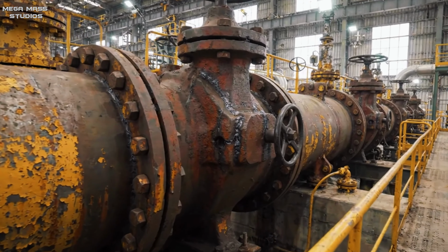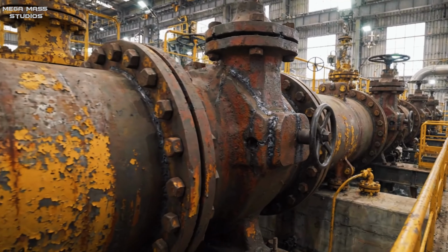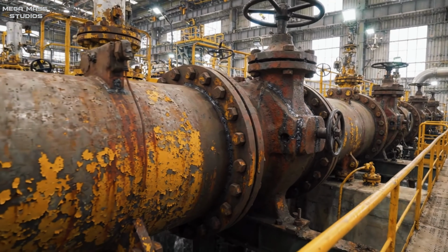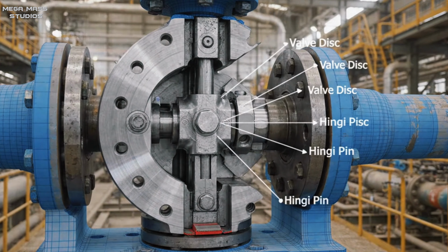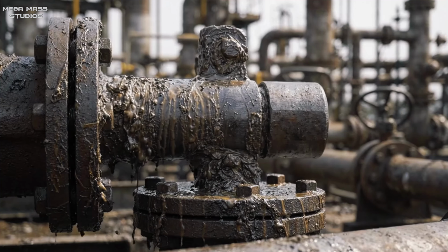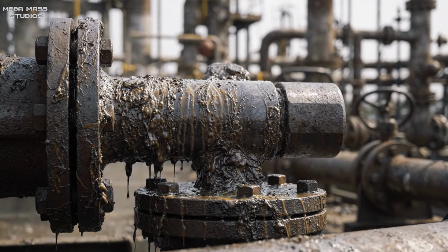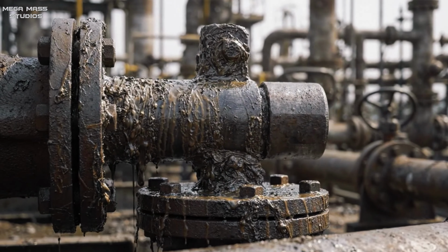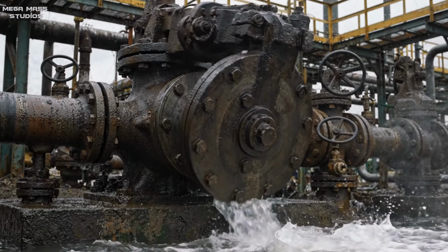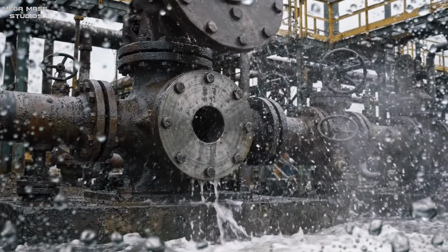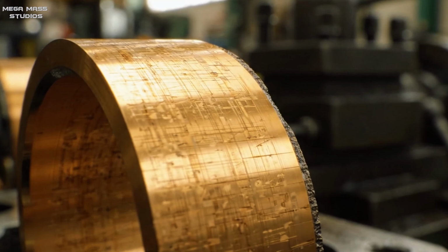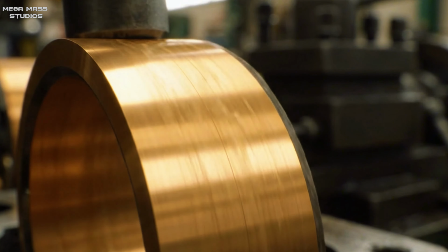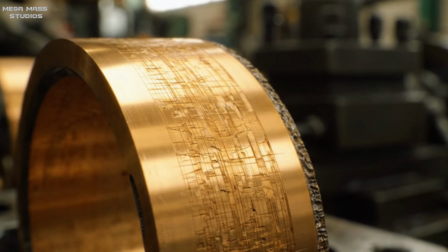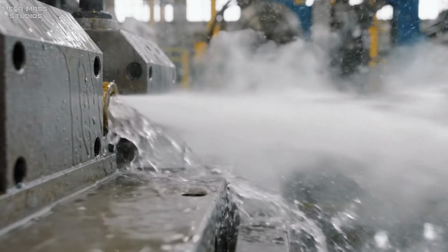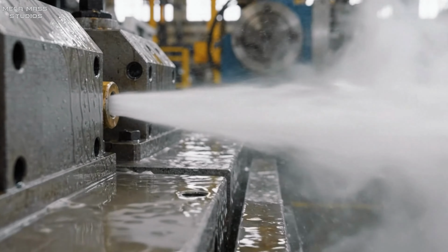Beside the active gate valves, massive mechanical swing check valves prevent instantaneous backflow from the river outlet. These check valves feature a heavy steel disc suspended on an internal overhead hinge pin assembly. As long as the pump discharge pressure is maintained, the steel disc is forced into the open position. If the flow stops, gravity and back pressure instantly swing the disc shut against the heavy bronze valve seat. The physical sealing surface of the valve seat is precision lapped to prevent even the smallest water leak. Any reverse leakage under high head pressure would erode the valve sealing faces through high-velocity jetting.